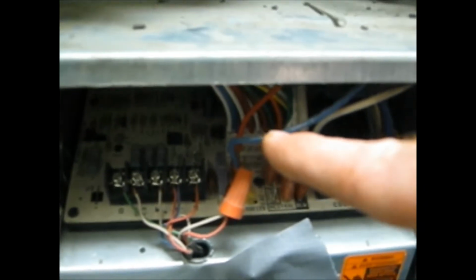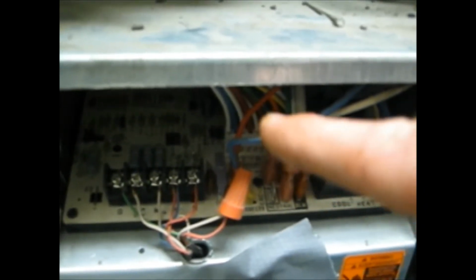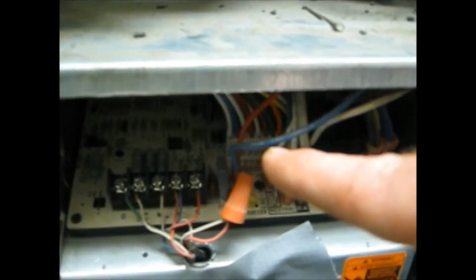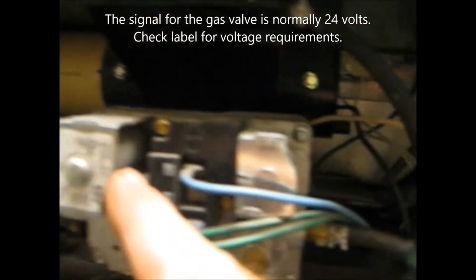Once the circuit board is satisfied that there's enough air pressure, this will do one of two things. The first thing it will do, it'll send a signal back up to that device in the back. That is a hot surface igniter. The part that sticks into the combustion chamber will get really, really hot. The next thing that will happen, the circuit board will send a signal to the gas valve to open up. So gas will flow through the gas valve up into the burner assembly, up to the hot surface igniter, and will ignite. It's relatively pretty simple.